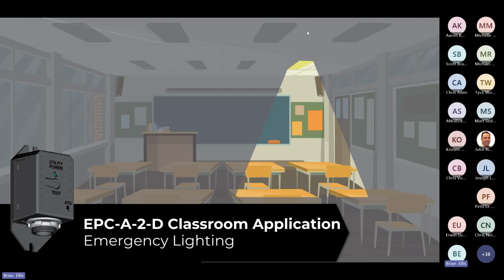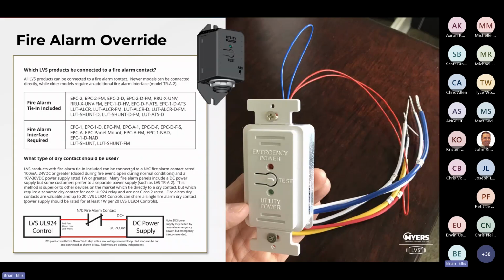What that does, if the customer understands what's happening, they're going to love it because they're testing their emergency equipment every time they use the space. If they don't know about it, then they might not like that functionality. If you flip this switch to the other position, the off position, it gets rid of the automatic test switch, so that visual test goes away. If you're using the non-A device, the older devices, the EPC2 or 2D, then you have this blue loop. If you cut the blue loop, that automatic test goes away.